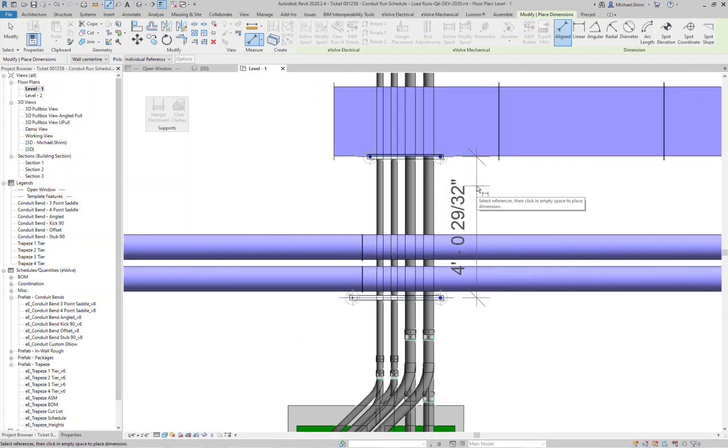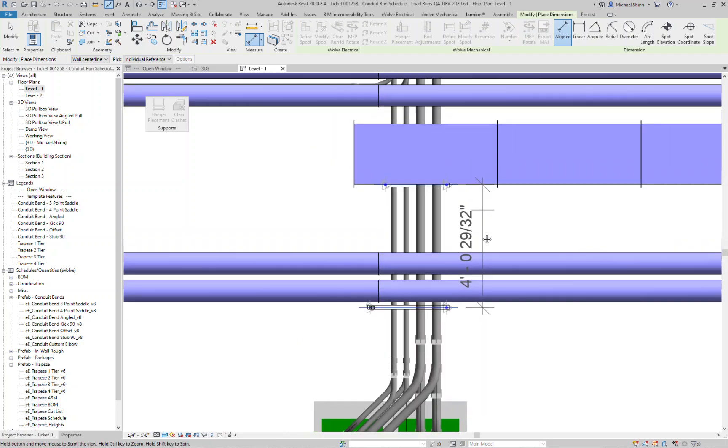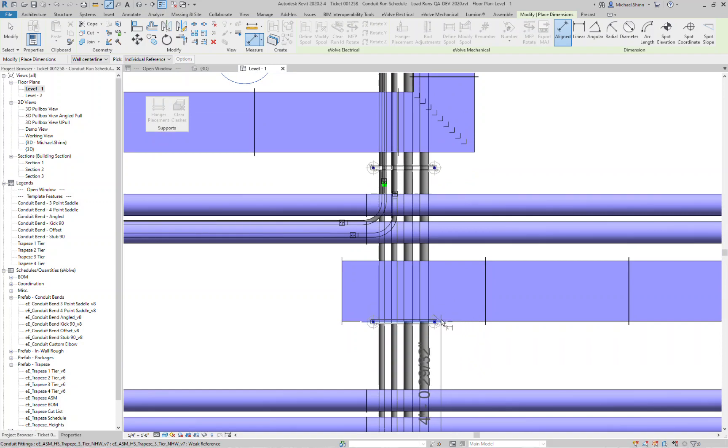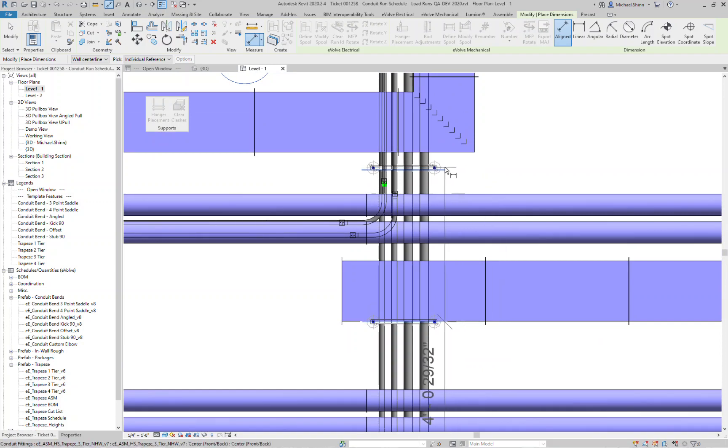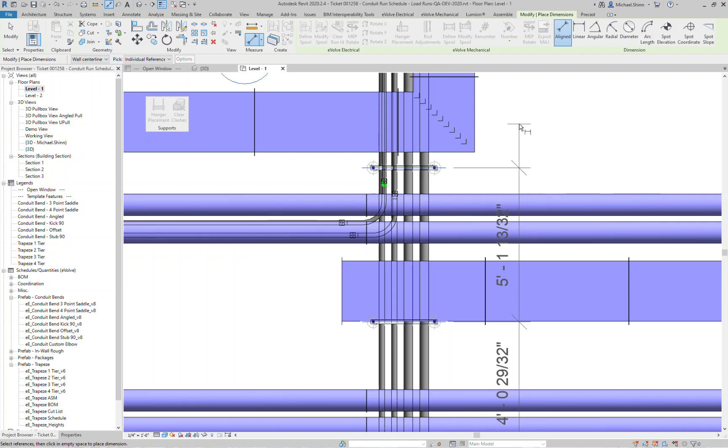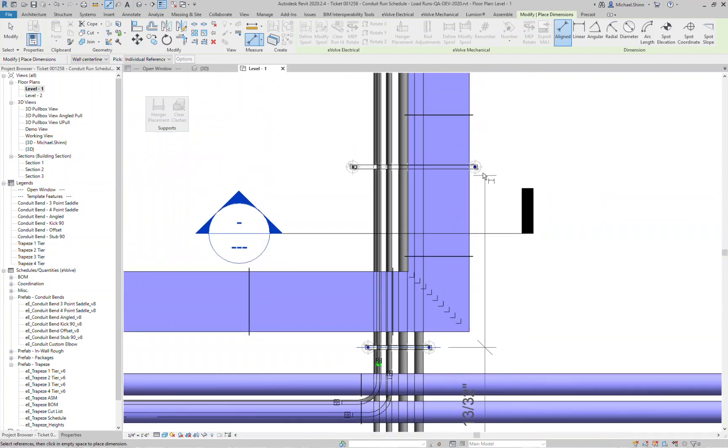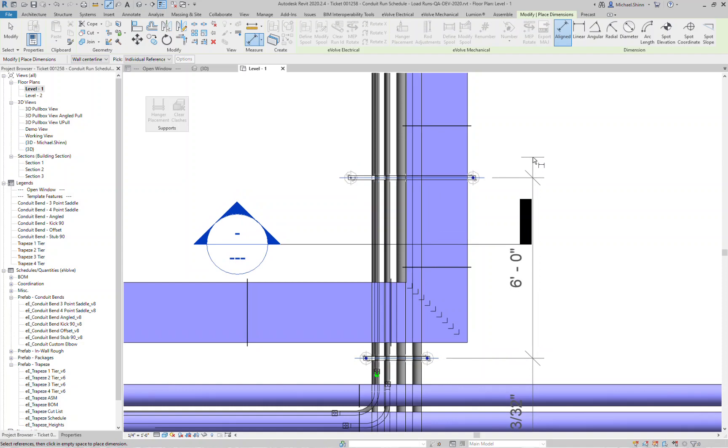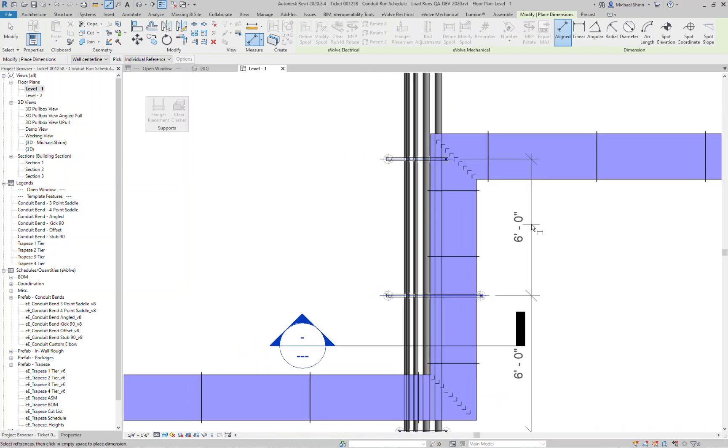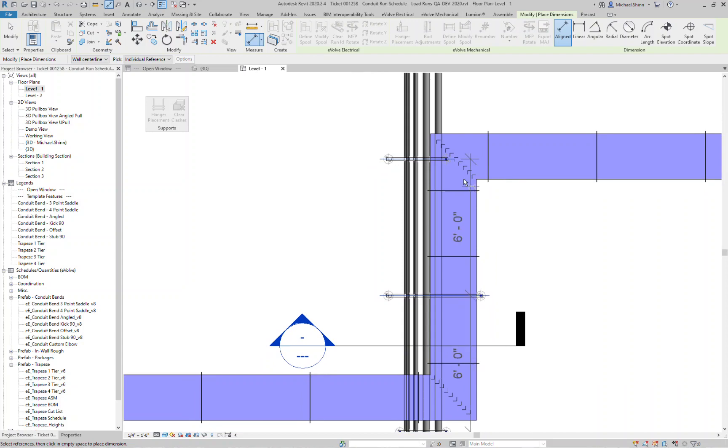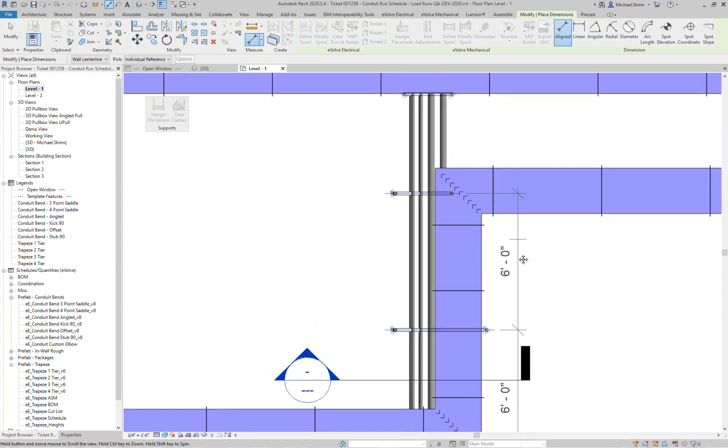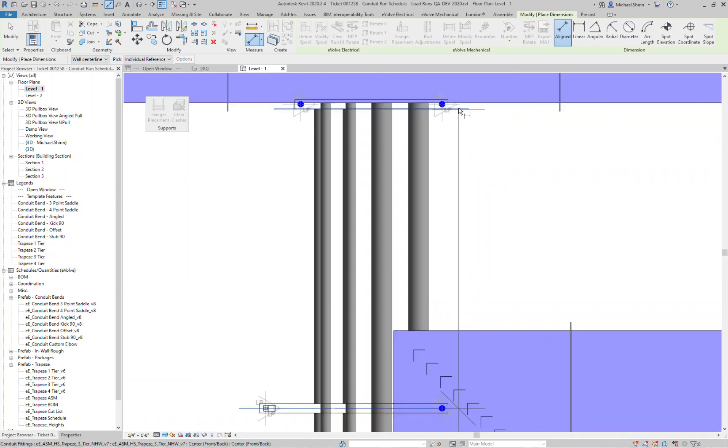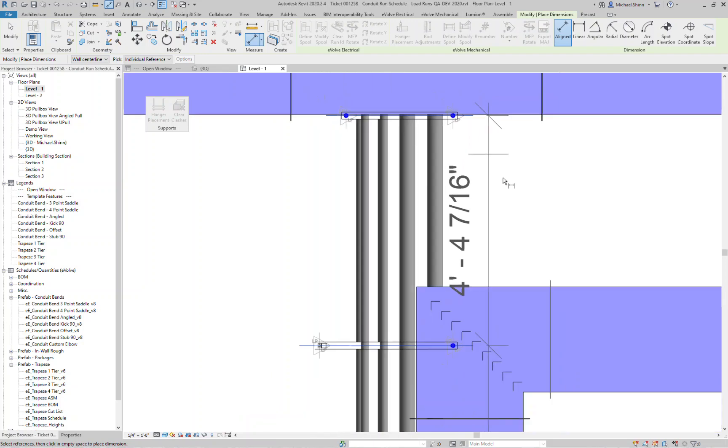So you can see we're supposed to place these every six feet. It moved that hanger and avoided that one, so now from that point the next one should be at six feet unless there's a clash. Yep, there would have been a clash so it moved that over. Next one, this one should have been at six feet, perfect, so that one stayed at six foot but it just adjusted the width for us. And then the next one here, let's grab this guy. This is the one that it highlighted. It didn't know what to do in this scenario because no matter what it did, if it moved it closer it would have caused a clash as well as potentially moving or adjusting any of the widths. And then so on and so on, it basically kept placing and adjusting all the hangers for us automatically.